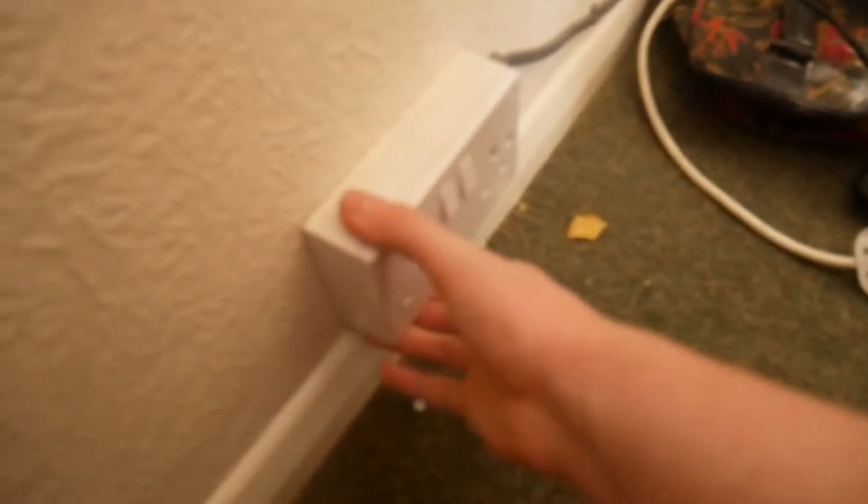You may remember a few episodes ago - 15 or 20 whatever - we put a socket on this side of the wall. It has worked for ages, however it's a stupid location. It needs to move somewhere around here because it's not practical behind this sofa. It's also stupidly low down. My nan requested another one to be added, so I'm going to do that via a fuse connection unit via a spur once from the ring main. We've done that from the front room socket - if you want to go any further you use a fuse connection unit, so fuse connection unit it is.